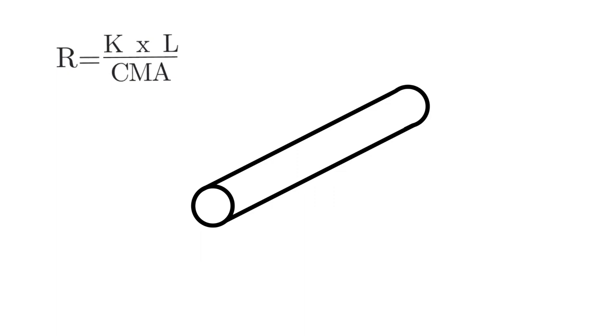But you can also have brass, cadmium, copper weld, iron, nichrome, silver, steel, tungsten—there's a bunch of them out there. So that's the constant, the resistivity constant, so that's your K. Length is going to be the length of the conductor in feet, and CMA is going to be the circular mil area of the conductor.